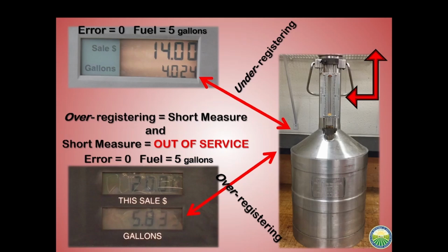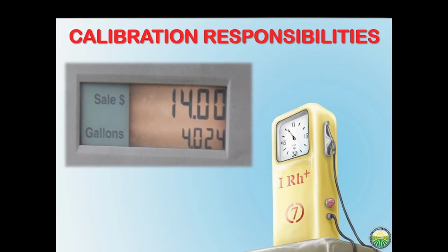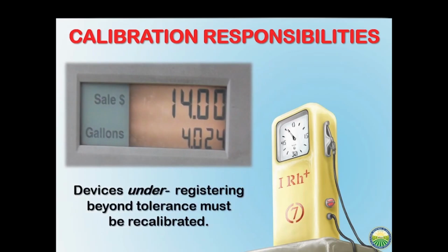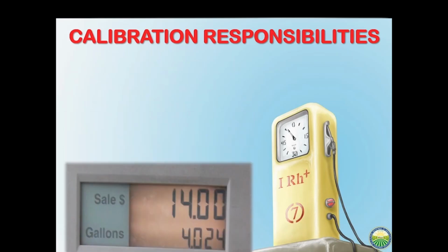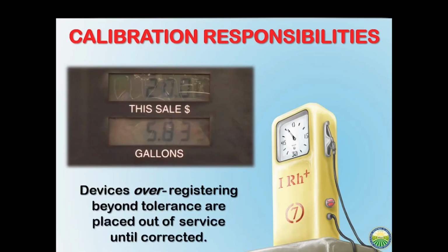Maintenance tolerance on a 5-gallon test measure is plus or minus 6 cubic inches. Acceptance tolerance on a 5-gallon test measure is plus or minus 3 cubic inches within 30 days of installation or return to service. If any petroleum-fueled measuring device is found to be under-registering fuel in excess of the specifications and tolerances established by the department, the inspector shall give in writing the operator or owner of the device up to 5 days to fix or adjust the device.